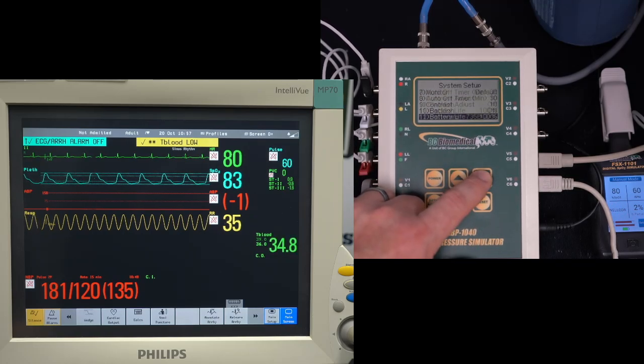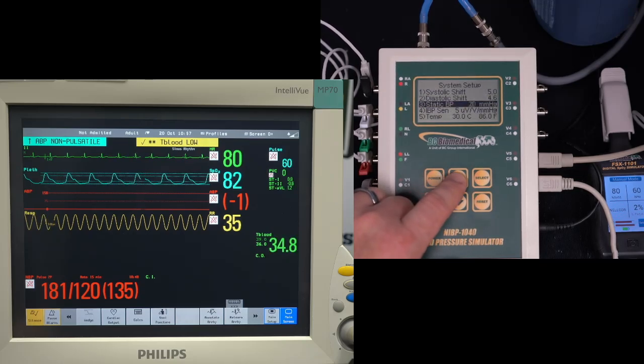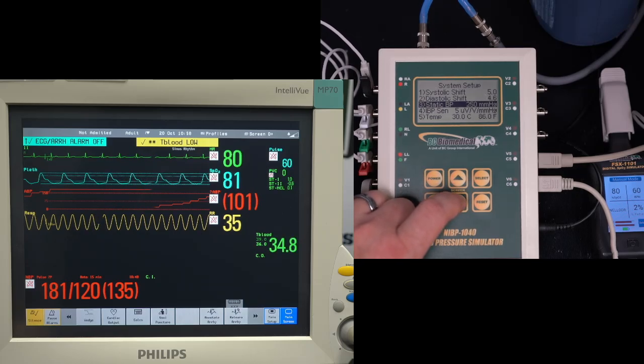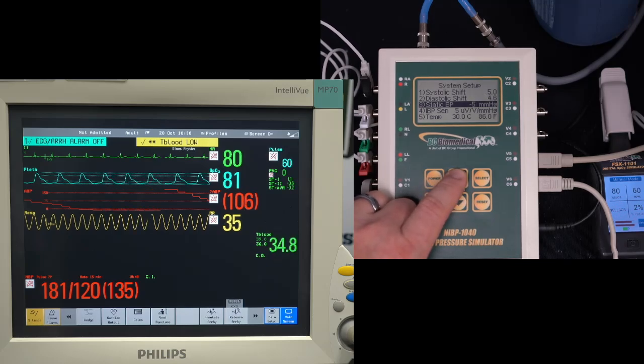And I'll scroll back through to the static. I'll just show you, we have quite a few static pressures available. So when you're testing your monitor, you can get a really good linearization test. And then for dynamic, we also have quite a few dynamic waveforms available. Those were on the main screen, but this is all of our static pressures here.